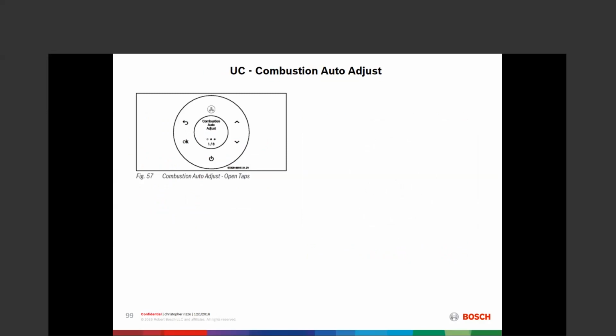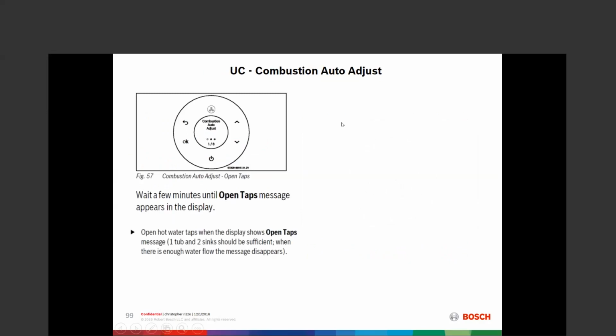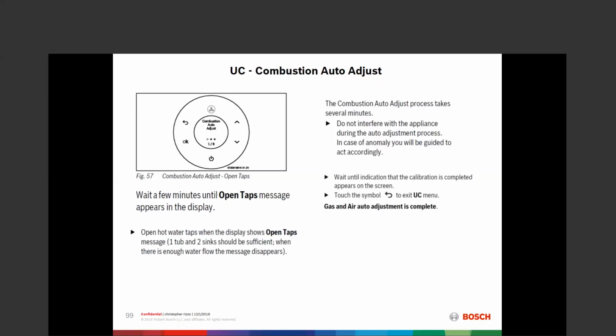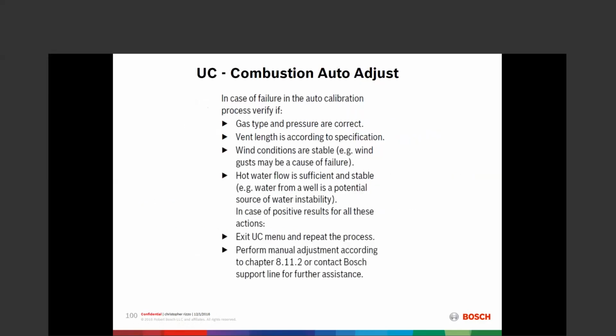It is 8 steps, and the only interaction from the contractor would be if there is not enough water flow, it will give the message open taps. That says, hey, there's not enough water flowing through the unit. We need more water flowing, and that is the only interaction that the contractor in the field would have with this auto adjust process. That's it. And it is the most common reason why the combustion auto adjust fails, is that there's not enough water flow. There are a couple other ones if the gas type was wrong or the venting was out of specification or something like that, but that's the most common one.